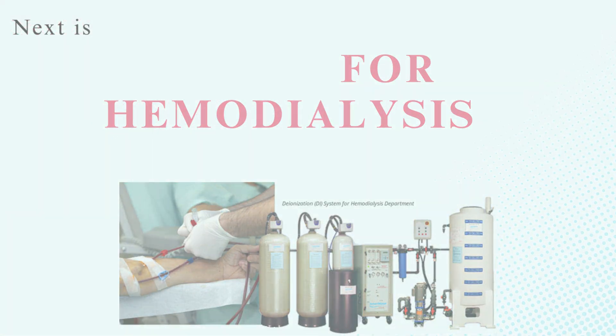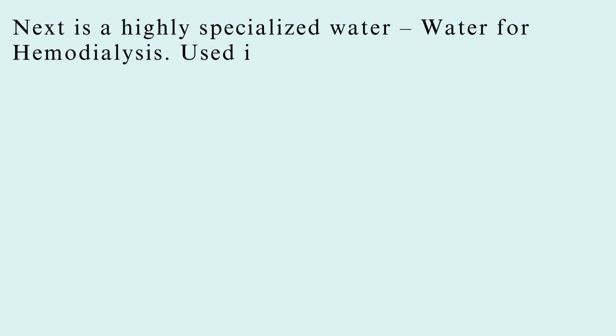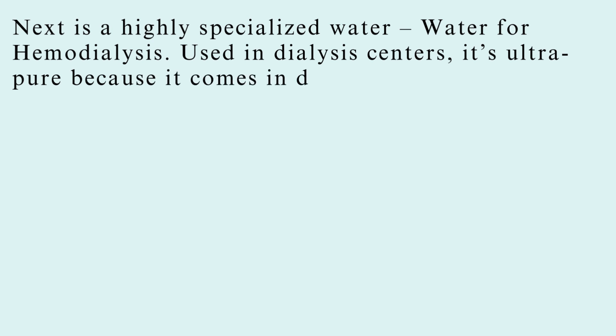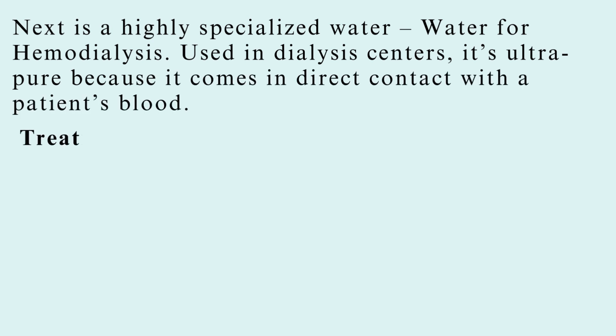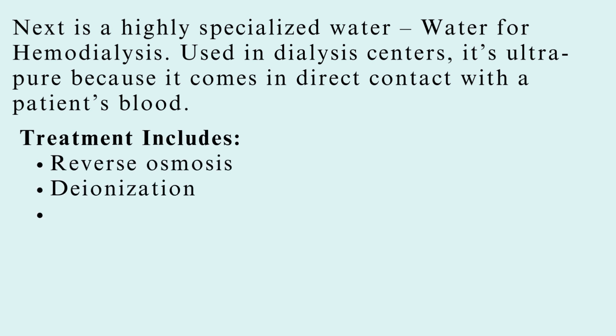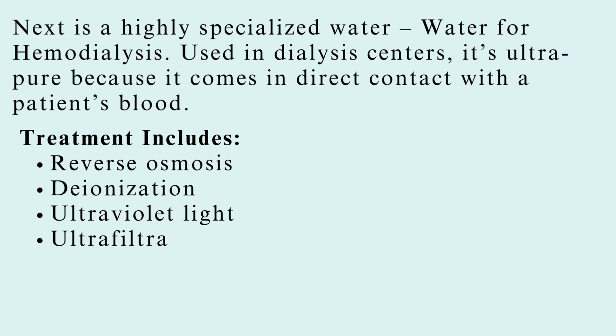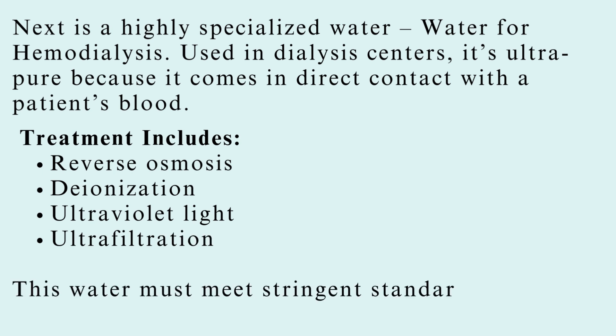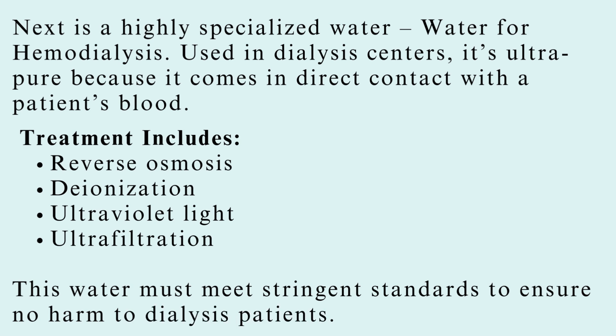Next is a highly specialized water: water for hemodialysis. Used in dialysis centers, it's ultra-pure because it comes in direct contact with a patient's blood. Treatment includes reverse osmosis, deionization, ultraviolet light, and ultra-filtration. This water must meet stringent standards to ensure no harm to dialysis patients.